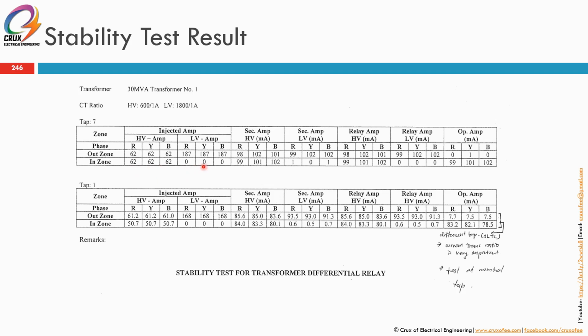Whereas when there's an in-zone fault, the primary side of the transformer is seeing some current, 100 milliamps, while the secondary side is not reading any current, so there will be an operating current which may be enough to trigger the differential. Normally this will be done and tested at various tap positions for transformers. Okay, so what is written here? Differential tap. So current transformer ratio is very important. Test at nominal tap.